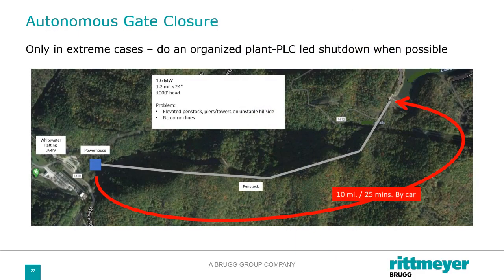Now, an autonomous system is different than autonomous gate closures. An autonomous gate closure means that the gate will close even when the plant PLC is not in commission or not able to talk to the gate. Normally, you want to be very careful with this, because if you have a false trip or even a real trip and you close this gate while there's still flow, you can collapse the penstock, or you can dry up the bearings and cause a lot of damage. So more than just having to repair a penstock, you now have a lot of work to do. So whenever possible, you want the plant PLC to lead the shutdown in a nice, organized manner.